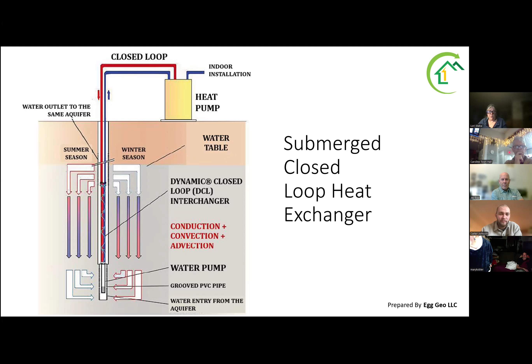So our analysis results were: if the formation is capable of producing 200 gallons per minute, which is right where we think it should be, our analysis suggests that an array of these submerged closed loop heat exchangers would require at least 8 wells in an area of about 20,000 square feet. So less wells and less square feet needed if we decide this technology is the way we want to go.